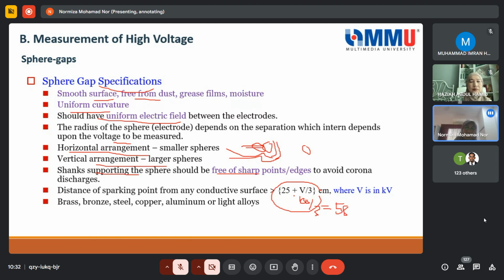This clearance is actually different from one equipment to another. So that's why in high voltage, sometimes they use a common clearance. Why do we need this clearance first of all? You know that the breakdown, if we take it ideally, is 30 kV per cm. So if you apply 30 kV, for example, to a sphere gap of 1 cm, then it will break down. But if you apply 20 kV and this is 1 cm, this will not cause a spark between the plates here.